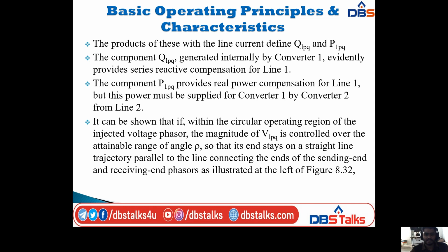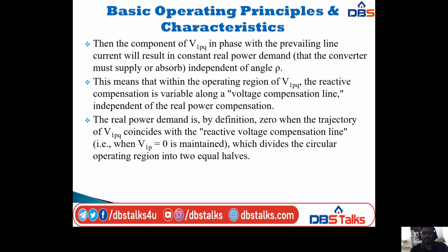Okay, so I will illustrate the left of the figure 8.32. And next, the component of V1PQ in phase with the prevailing line current will result in constant real power demand, that is independent of angle rho. So this means that within the operating region of V1PQ, the reactive compensation is variable along a voltage compensation line independent of the real power compensation.